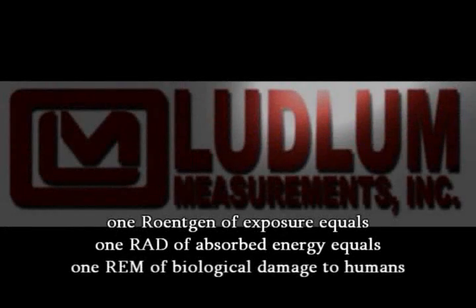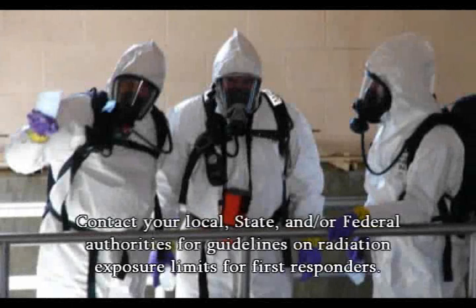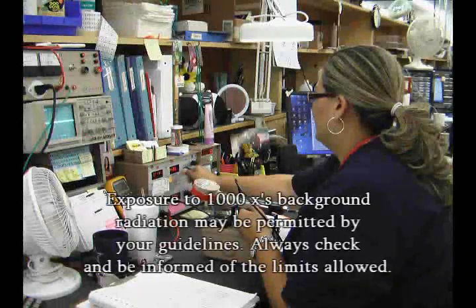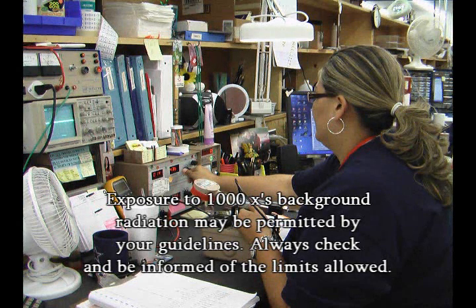For gamma radiation, 1 Roentgen of exposure is approximately equal to 1 rad of absorbed energy. This equals 1 rem of biological damage in humans. Contact your local, state, and/or federal authorities for guidelines on radiation exposure limits for first responders. Due to the sensitivity of the instrument, it is possible to measure radiation levels that are not generally considered to be hazardous to health. Exposure to radiation levels of even 1,000 times normal background radiation or more may be permitted by your guidelines without any health effect.